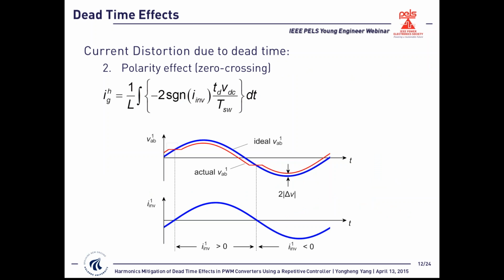But of course, we also have to apply the harmonic controllers. The other current distortion reason is the polarity effect from the inverter output current, as shown in this figure. We can see here that when the inverter output current is positive, there will be a voltage reduction. I mean the fundamental voltage of the inverter output will be reduced, while when the inverter current is negative, there will be a slight increase of the inverter output voltage. But in general, there will be voltage loss in the inverter output voltage.